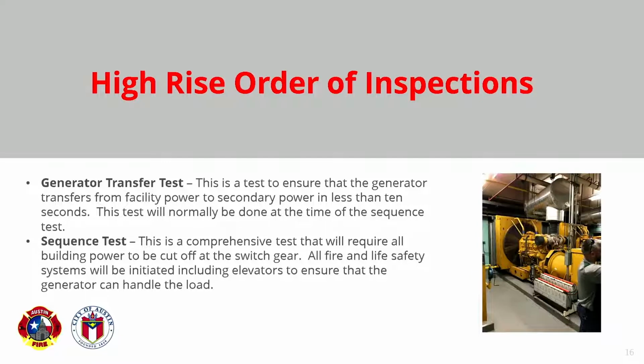The generator transfer test, there's not much to it. We're just testing to ensure that all the transfer switches work and that the fire and life safety systems' ATS transfers over in less than 10 seconds. We're normally going to do this test at the time of the sequence test, so that you only have to have your generator technician out one time. So normally it's not an issue. As long as the generator technician's there, if there are any issues, we're normally able to work them out on site during the sequence test. So that leads us to the sequence test.